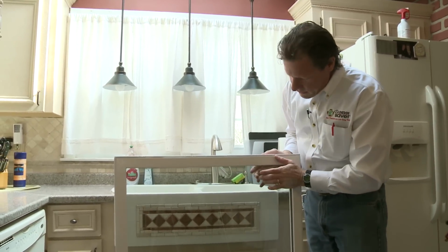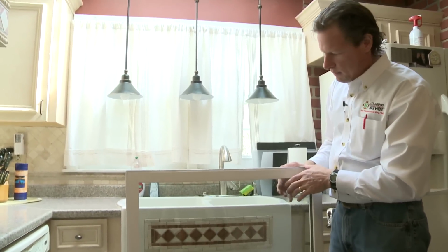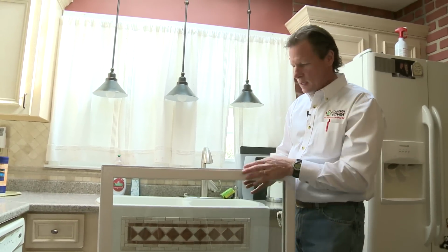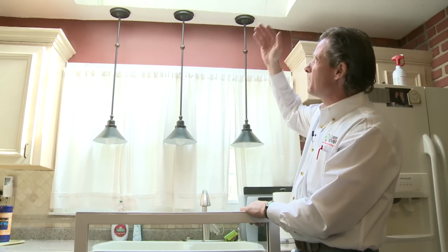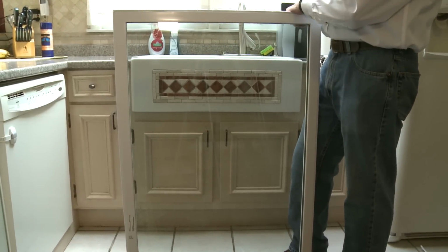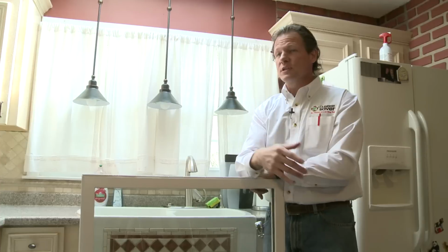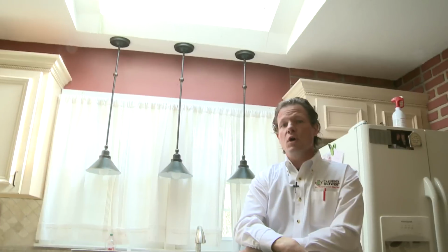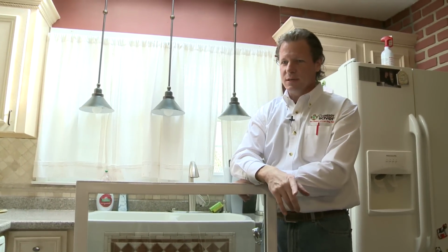And this pane is 2 panes of glass. So it is also argon filled so that we don't get heat transfer from one pane of the glass to the other. But basically we're going to have a triple layer. We have the skylight, and we have 2 panes of high performance low E glass here, and a 6-inch air space in the middle, and we will dramatically improve the situation, making the bottom surface of this glass much warmer in the winter and much cooler in the summer.